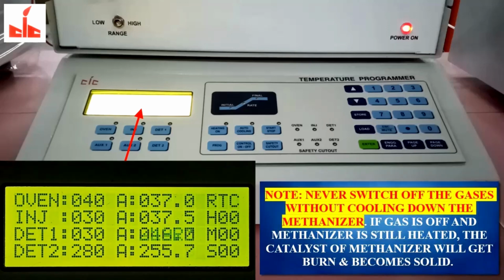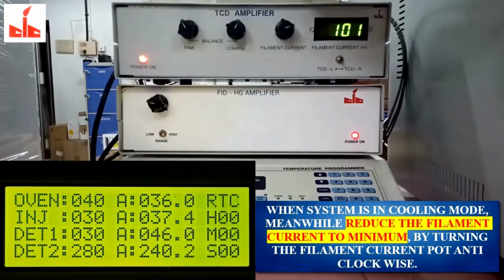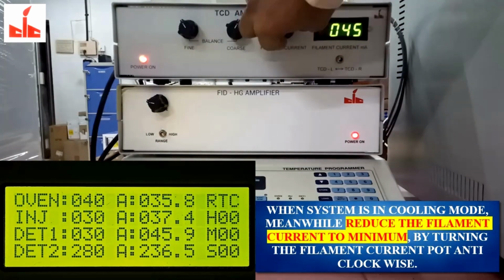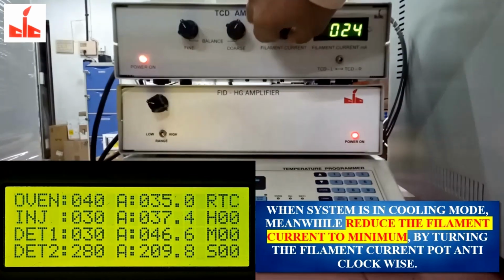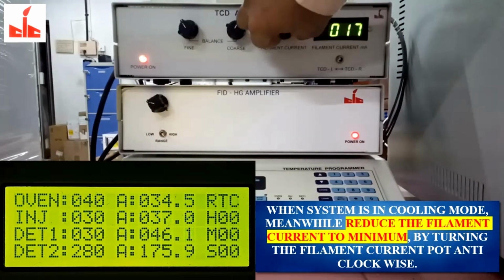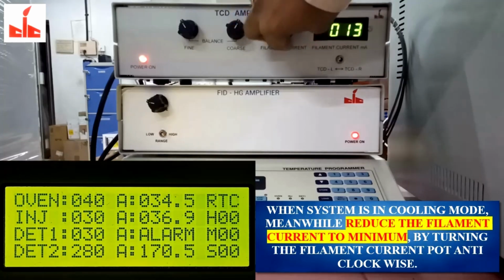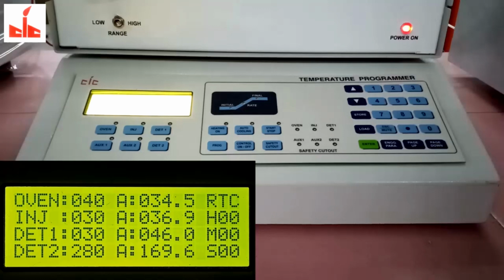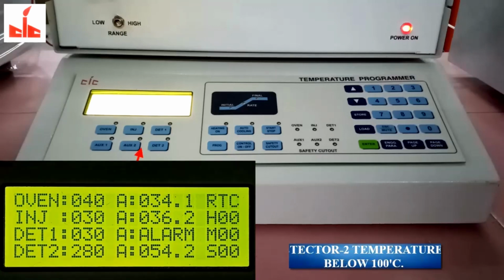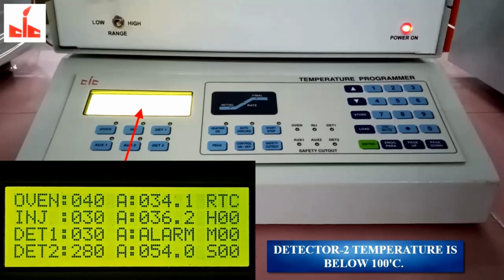Never switch off the gases without cooling down the methanizer. If gas is off and the methanizer is still heated, the catalyst of the methanizer will get burned and becomes solid. So wait till the detector 2 temperature reaches below 100 degrees centigrade. When the system is in cooling mode, meanwhile reduce the filament current to minimum by turning the filament current pot anti-clockwise. Detector 2 temperature is below 100 degrees centigrade.